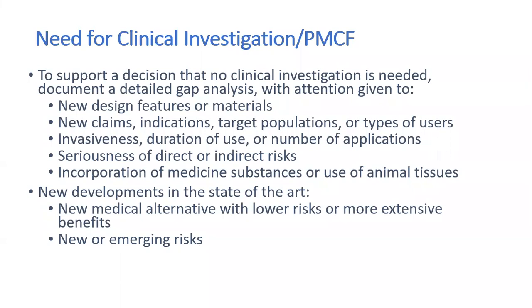This is the best route by which we can demonstrate the safety and performance of the device, the clinical evaluation route. Coming to the next is the need for clinical investigation or PMCF activity. To support a decision that no clinical investigation is needed, document a detailed gap analysis with respect to new design features or materials, new claims, indications, and target populations. Even if there is a slight change in target population or design, or if any new claim comes up, or if there is any new clinical indication or types of users, you have to go for clinical investigation.